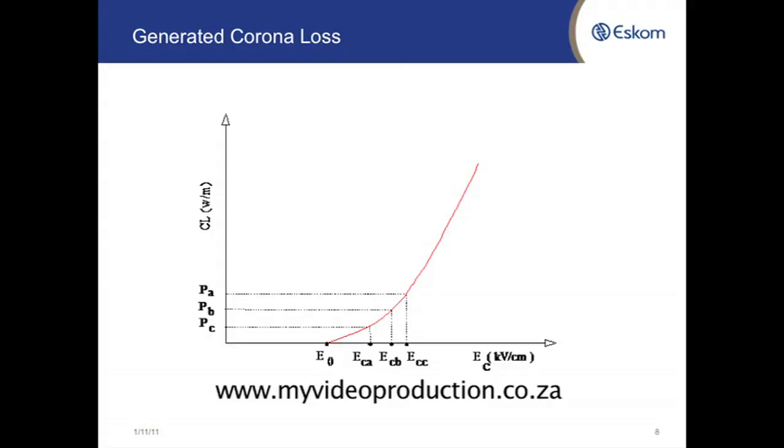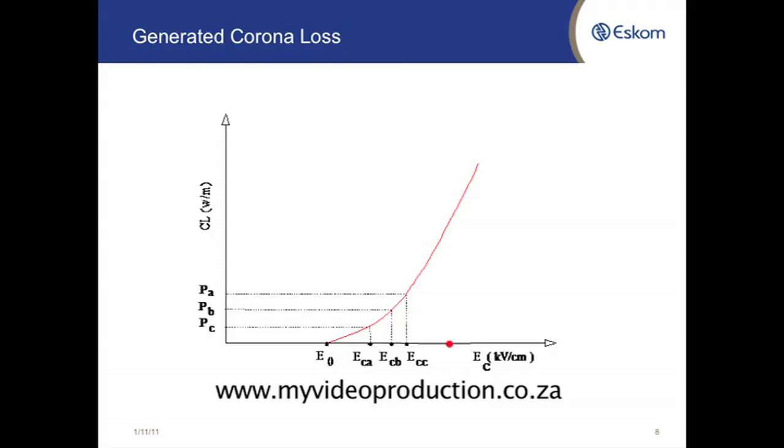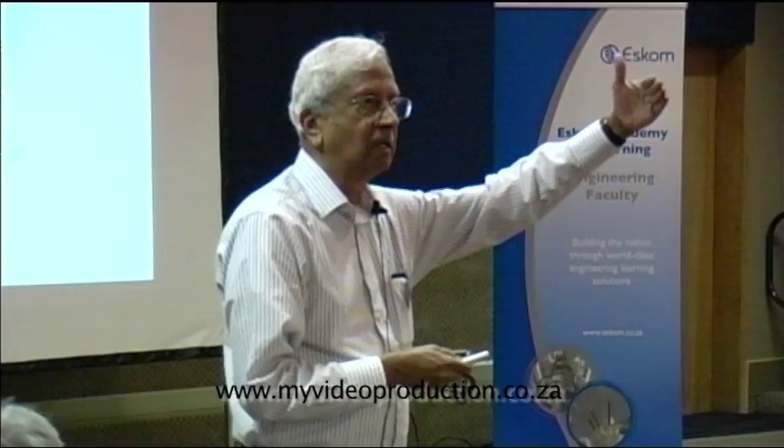So, this concept is very useful because when you are doing tests, you have a three-phase line and the gradients on the three phases are different. So, how do you calculate the three-phase corona losses from the tests? Suppose we have corona loss as a function of the conductor surface gradient — we can do it in the cage. You increase the voltage, measure the losses, so you can obtain this curve.